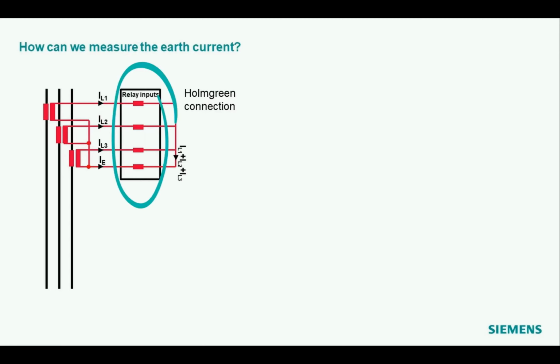This is a protection relay connected to the 3 current transformers on the cable or on the overhead line. And what I indicate here are the measuring inputs of the protection relay. We have 1 measuring input per phase. And then these 3 wires are connected here to a star point.